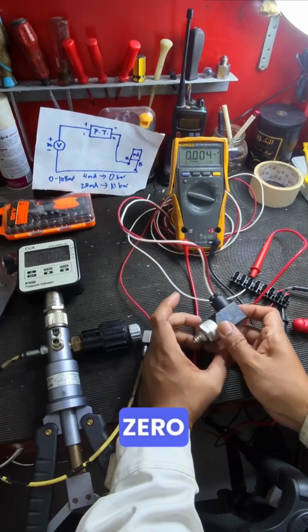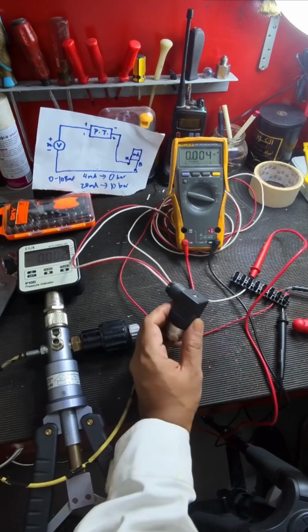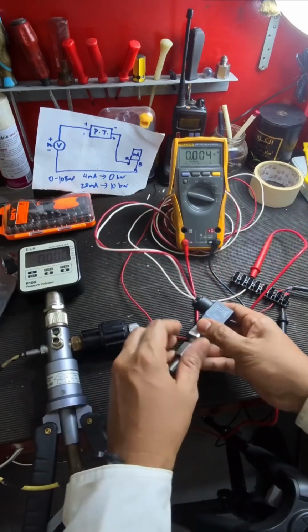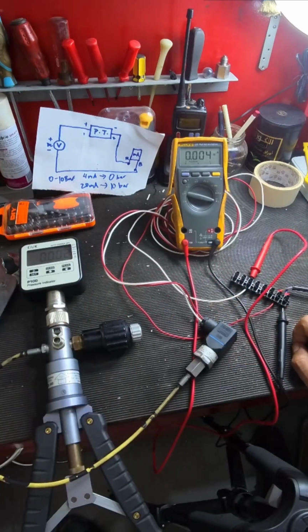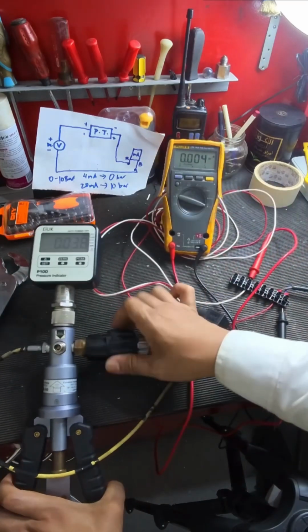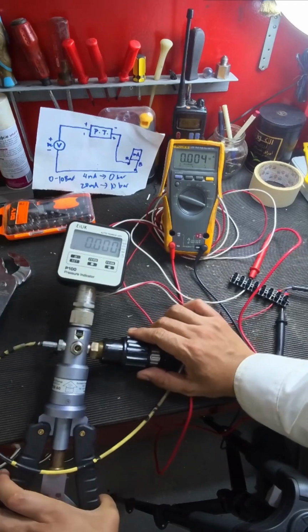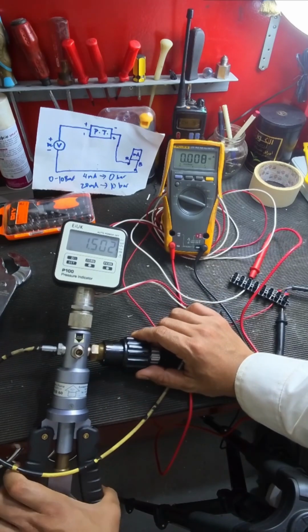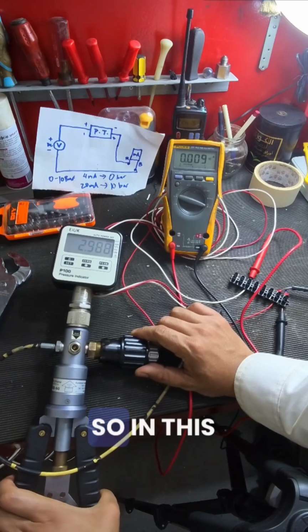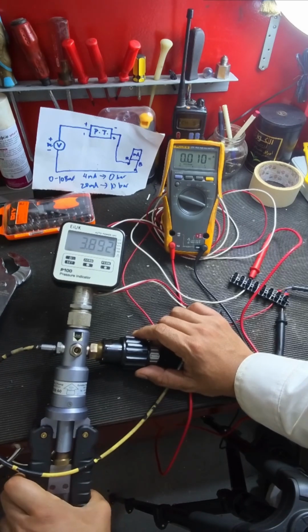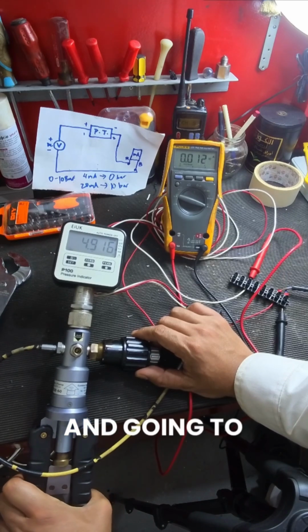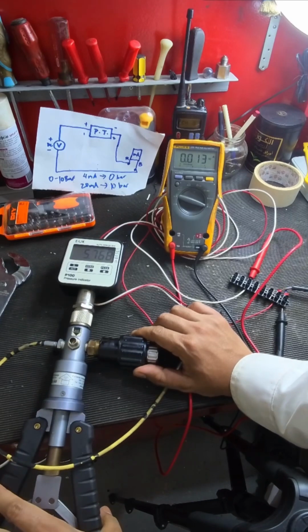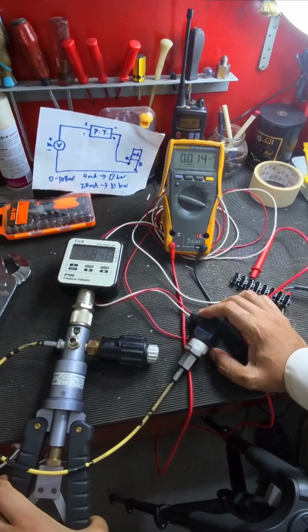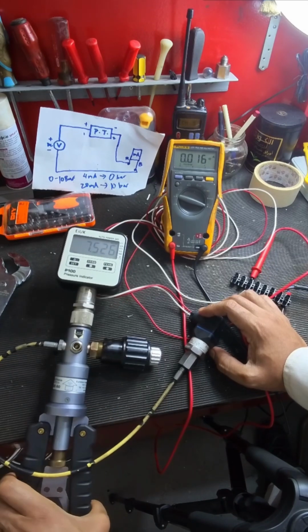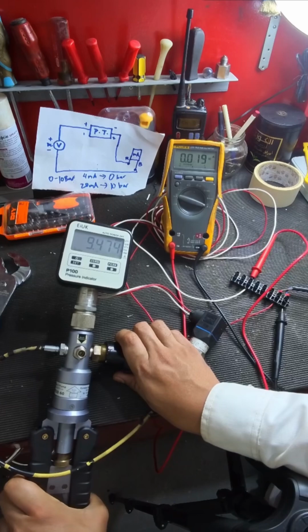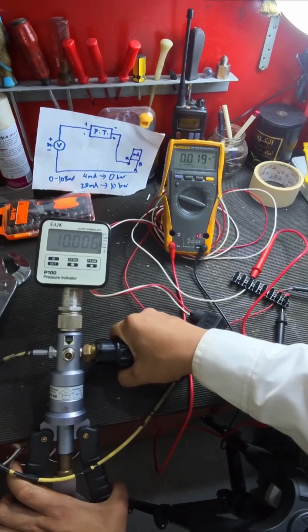Okay, you see 0 pressure, 4 milliamps. So maybe this is good. Don't put overpressure on the sensor, guys, because there's a possibility of damaging the sensor. Alright, in this case, guys, it's very fast responding and good at following the pressure. So maybe this sensor is good. Yes, okay, I can solve the issue. Oh, very good.